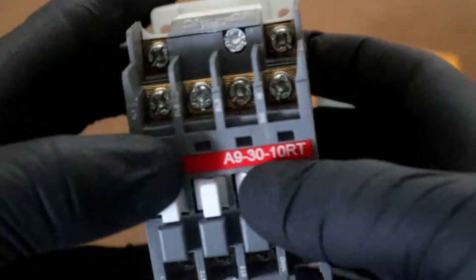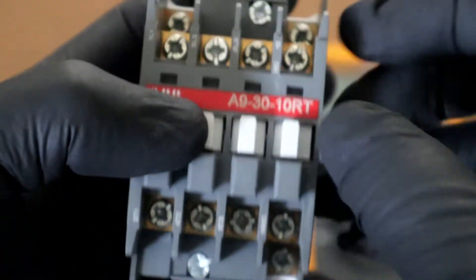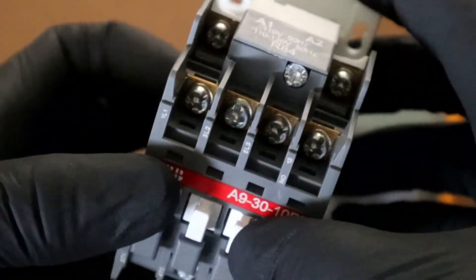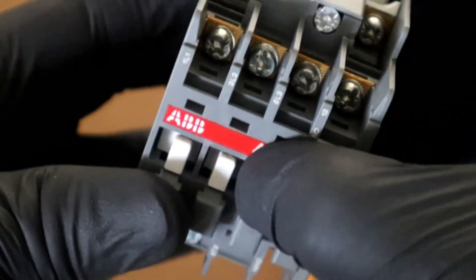Inside here we have a spring called a return spring. That is also a significant failure point of contactors. If our spring fails that will prevent our coil from actually closing and opening our contactor, preventing it from operating as it's supposed to operate.